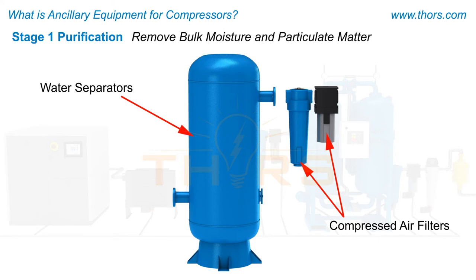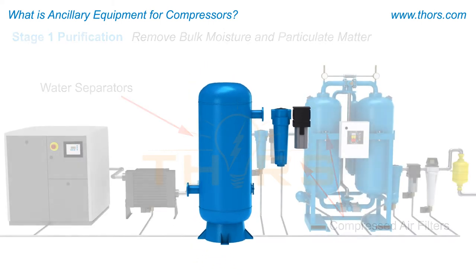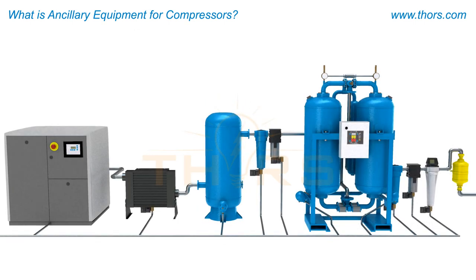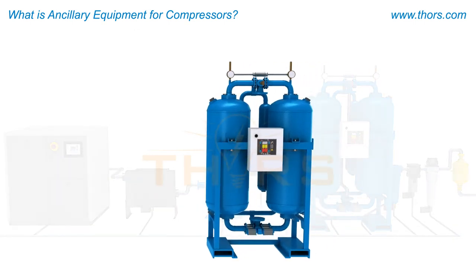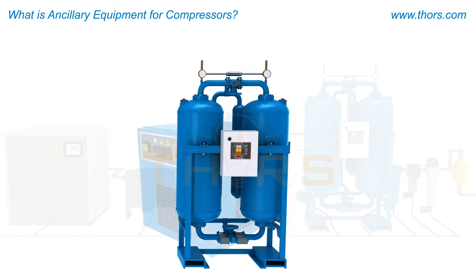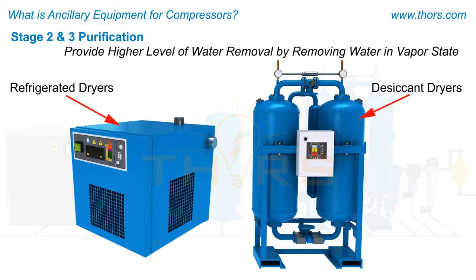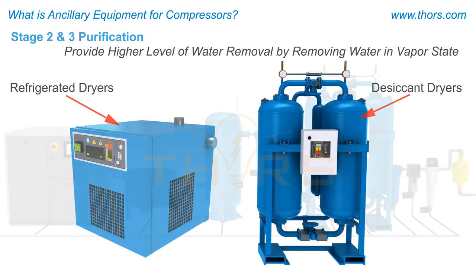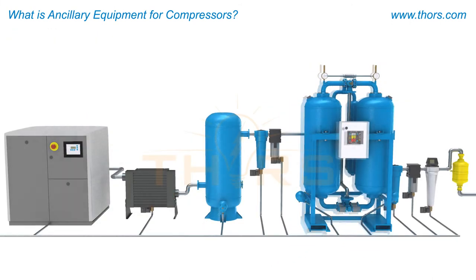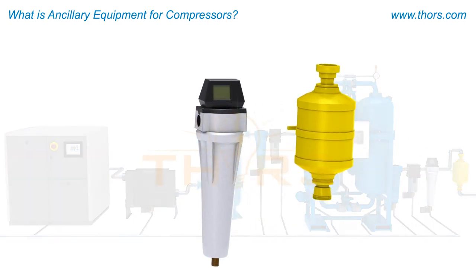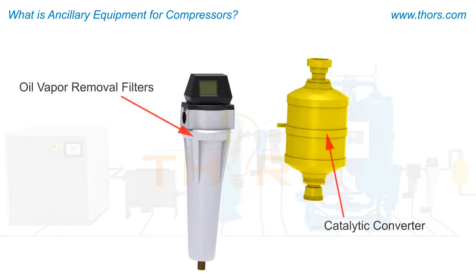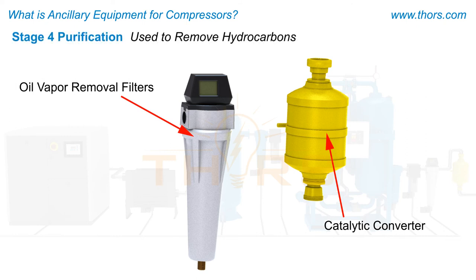Refrigerated dryers and desiccant dryers are used during stages 2 and 3 respectively to provide a higher level of water removal by removing water in the vapor state. Catalytic converters and oil vapor removal filters — also known as activated carbon filters — are used during stage 4 to remove hydrocarbons present in the air.